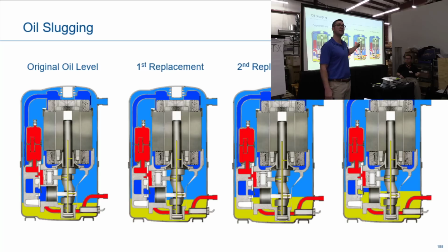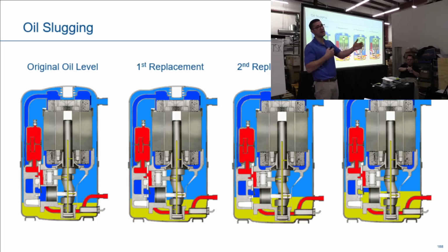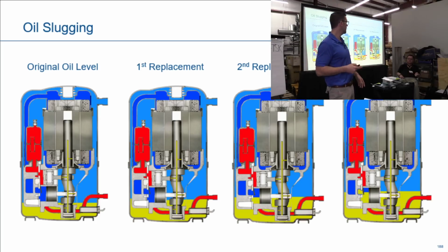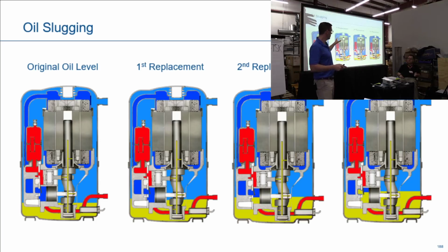This could be a low temp application. What happens to oil when it's really cold? What does it get? Viscous. Very viscous. So it doesn't move the same. Right? So all of a sudden you got a really cold evaporator and your piping is not that great and it all stays in the evaporator. Okay? All of a sudden that defrost happens, pulls all the oil back and then. So if the compressor's failed anyway, what you do is drill a hole in the bottom over the proper cup, fill it up and see how much oil is in it.